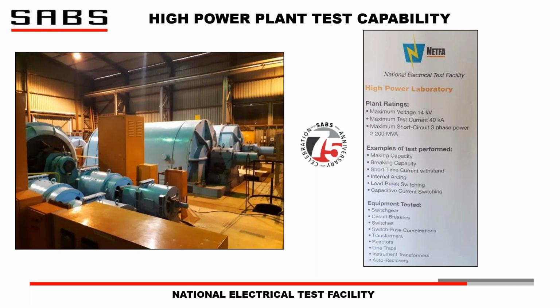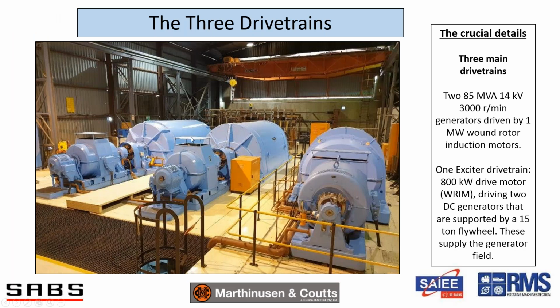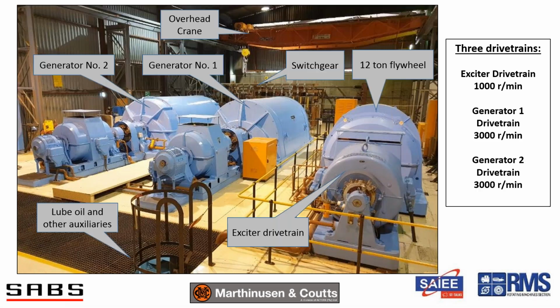Okay, there's three drivetrains in front of us here. There's the two generators with their drive motors, and then there's the excitation train on the right. The generators are 85 MVA, 3000 RPM, 14 kV units. They are very special, and they are also very old, but they are classic proof that the older stuff works better in many cases. Okay, a little bit more detail. The plant doesn't end at floor level. There's a lot below the floor, the lube oil unit and other auxiliaries. There's a jacking oil system that jacks all the bearings of all three drivetrains to the point that you can turn it by hand. And it's crucial that that system operates and is maintained correctly.